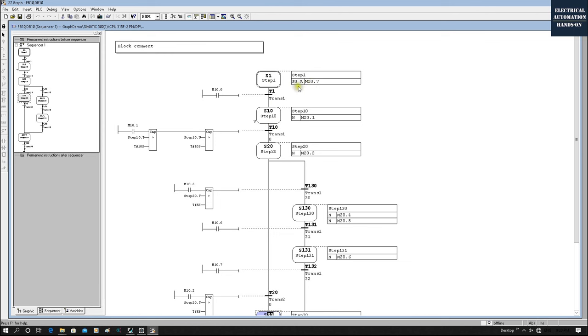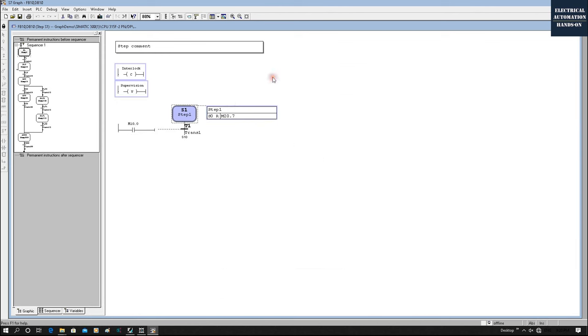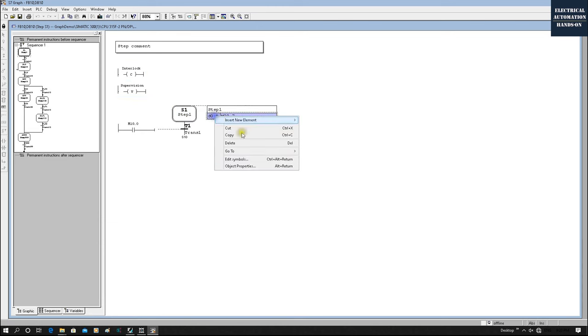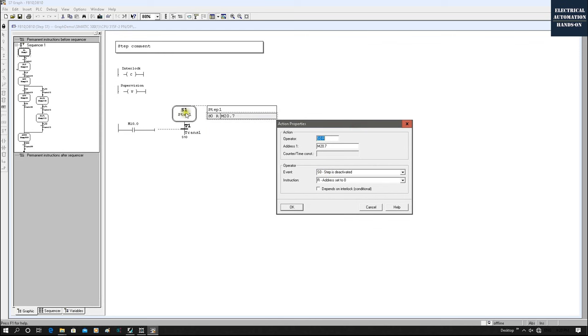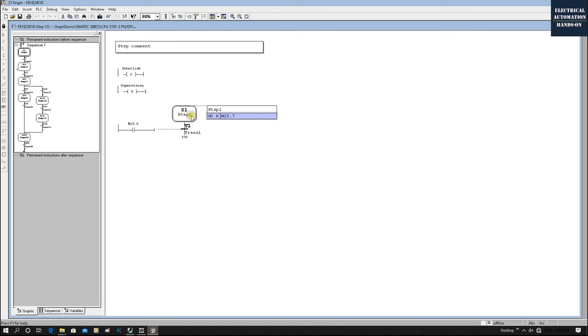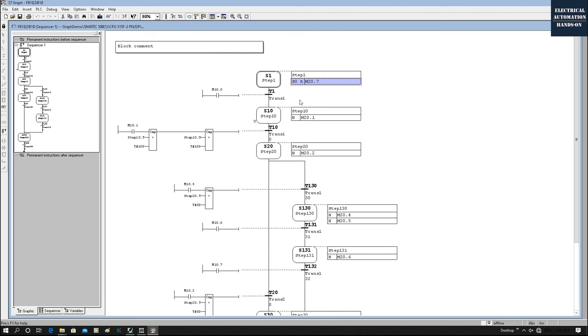At the first step we typically use S0 to reset the complete flag. Once we leave S1, we will reset this complete flag, because once we activate this sequence, S1 will stay and wait for the condition to move to the next step. S0 means the step is deactivated — once we leave S1, we will execute this reset. This is the first tip: typically we use one bit — either M address or DB address — to show this sequence is complete.